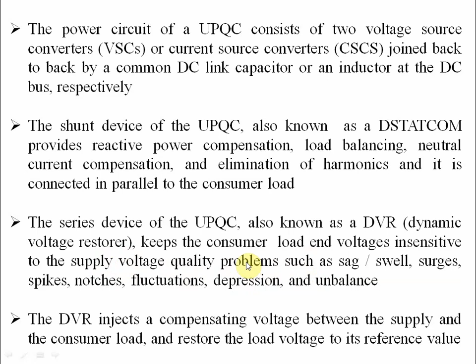So even if there are some problems from the utility side, the series device of UPQC, that is dynamic voltage restorer, keeps the consumer load end voltage insensitive. It means that the consumer load end voltages are not affected due to these supply voltage problems. So how does the DVR take care of this? The DVR injects a compensating voltage between the supply and the consumer load, and by doing so, it restores the load voltage to its reference value, that is the preset value. That's why it is insensitive to the voltage quality problems from the supply.